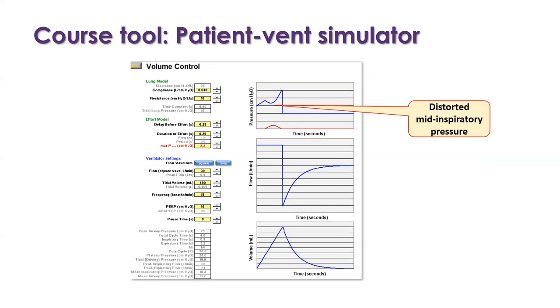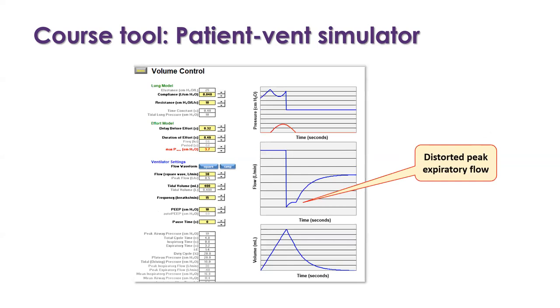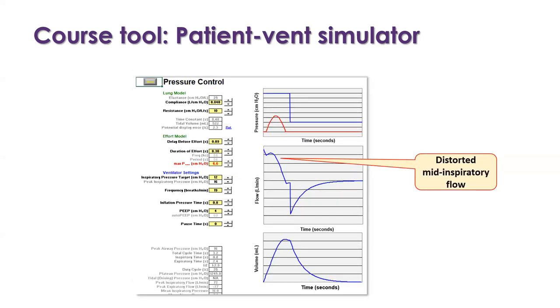Here's the same patient, but making an inspiratory effort after machine trigger event. This is a specific patient ventilator synchrony problem called early triggering, but also known as reverse triggering in the literature. This is a demonstration of another synchrony problem called early cycling. Note that the patient's neural inspiratory time, represented by the red PMUS curve, extends beyond the set inspiratory time. The classic sign is a distorted peak expiratory flow. Here is an example of how PMUS can distort inspiratory flow and volume waveforms in pressure control.